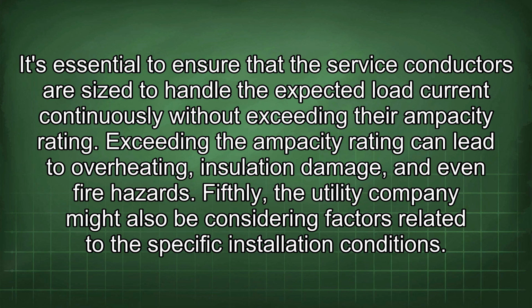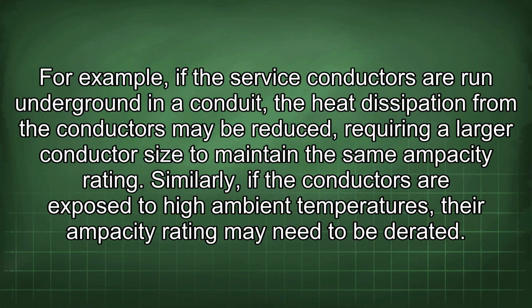Fifthly, the utility company might also be considering factors related to the specific installation conditions. For example, if the service conductors are run underground in a conduit, the heat dissipation from the conductors may be reduced, requiring a larger conductor size to maintain the same ampacity rating. Similarly, if the conductors are exposed to high ambient temperatures, their ampacity rating may need to be derated.